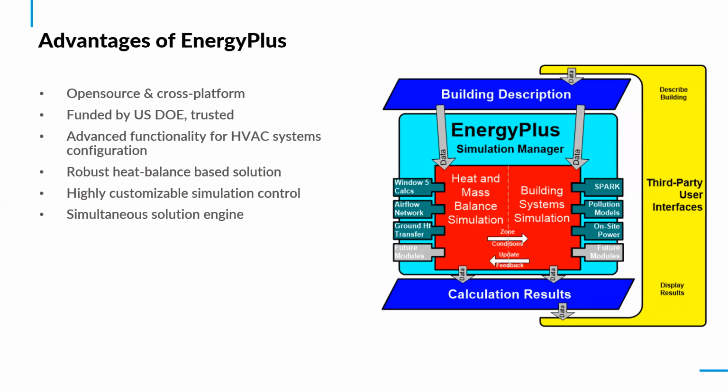It's a robust heat balance based solution. Again, highly customizable when it comes to simulation controls. A lot of that can be automated again for those everyday type users, and then users that need and want to be able to get into the exact calculation methodologies, the exact time steps, all of that stuff is open and available to them. And through load modeling, it's open and available, so they can edit that. And then finally, it's a simultaneous solution engine. So it's solving for room loads, zone loads, system loads, plant loads, all at the same time. So it gets you the correctly sized systems through the engine itself.